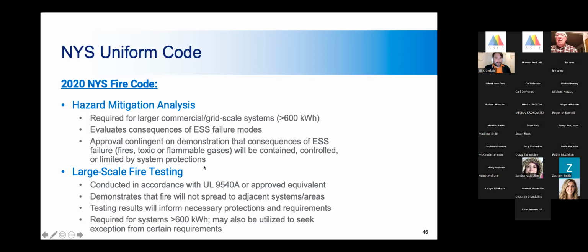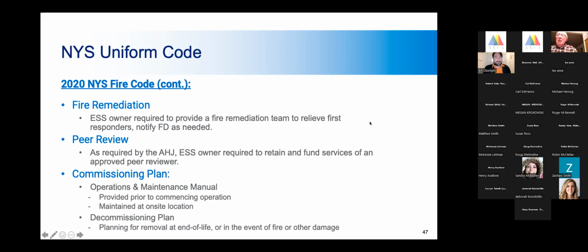It is required by the fire code: large scale testing for systems over 600 kilowatt hours. That's the UL 9540A test, and it only applies above 600 kilowatt hours. The testing results will inform protections and requirement necessities, and the results from the test will demonstrate the fire will not spread to adjacent system areas, not that there will never be a fire.